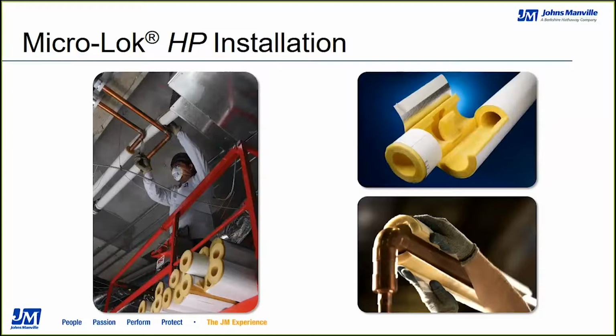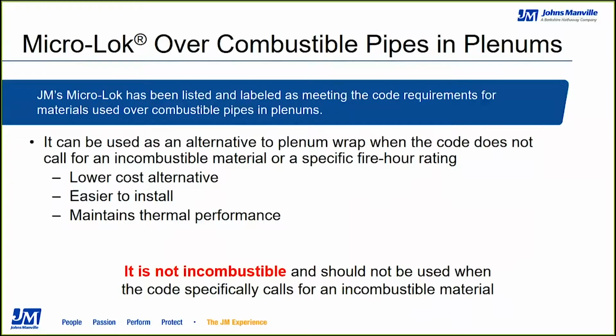And as you can see, the contractor in the picture on the left is easily sliding the pipe insulation onto the pipes, able to mark and cut the perpendicular scrim lines that come on our jackets, allowing for ease of installation, using the SSL to secure it in place, and then depending on the installation and the requirements, coming back and either stapling and covering with mastic or just relying on the SSL. JM's Micro-Lok has been listed and labeled as meeting the code requirements for materials used over combustible pipes in plenums. However, it is not incombustible and should not be used when the code specifically calls for an incombustible material.